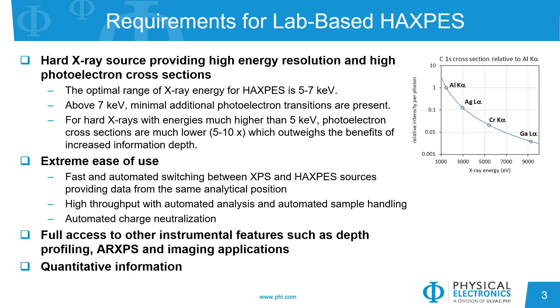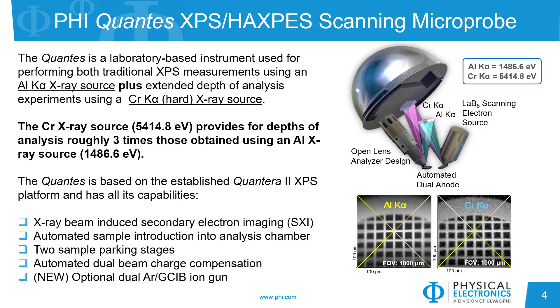Choosing the best photon source for HAXPES is a balance of information depth, photoelectron cross-section, and additional transitions gained. 5 to 7 keV has been found to be an optimal choice. Based on the established QUANTERA 2 XPS platform, PHI and ULVAC-PHI have developed the QUANTES, a lab-based XPS/HAXPES instrument which contains two X-ray sources: monochromatic aluminum for traditional XPS and monochromatic chromium for HAXPES analysis.